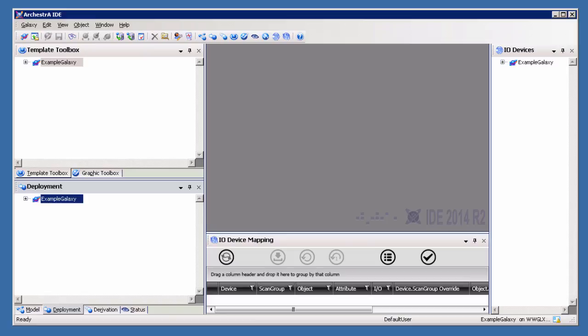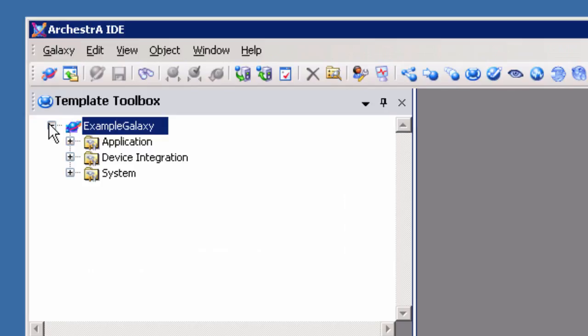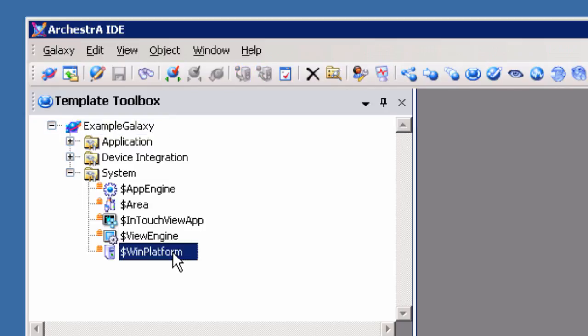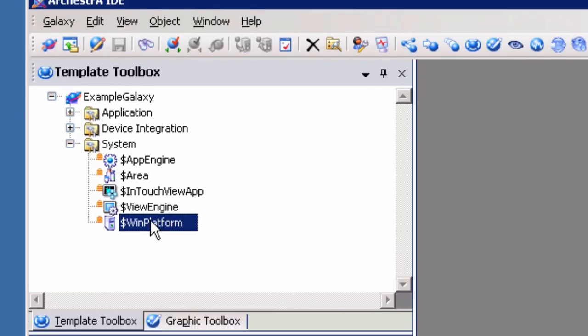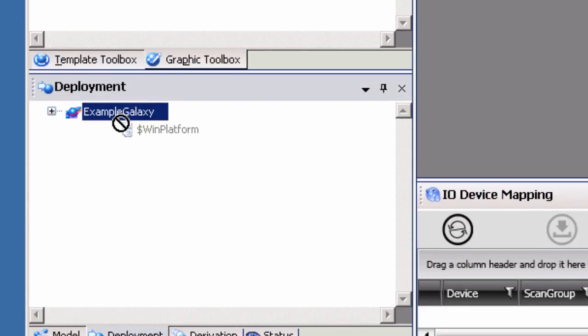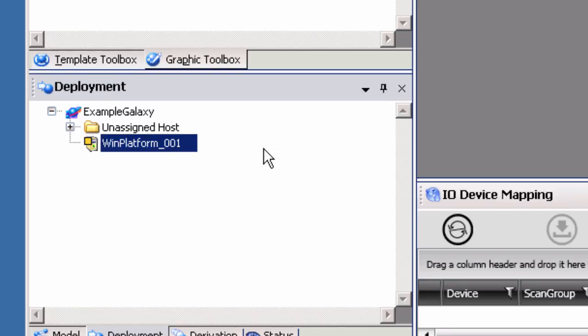For this example, we will be using the Deployment view in our sample Galaxy. The first step in configuring a new project begins with the System Object in the Template Toolbox. Expand the System Object and highlight the Win Platform Template Object. Drag and drop the Win Platform Template Object under the Galaxy in the Deployment view. This example will use the default names, but you can name these objects as needed for your project.